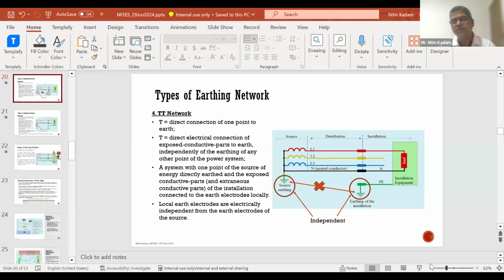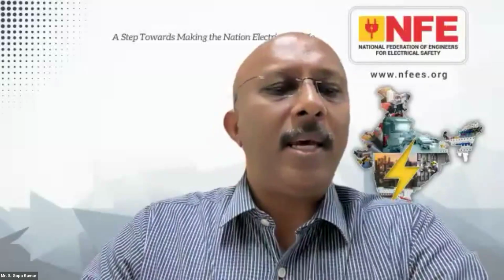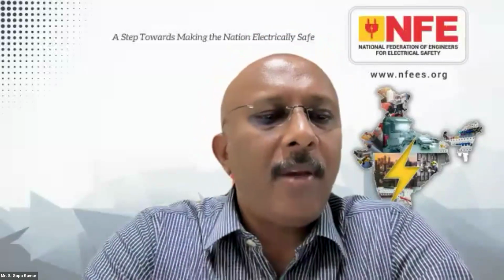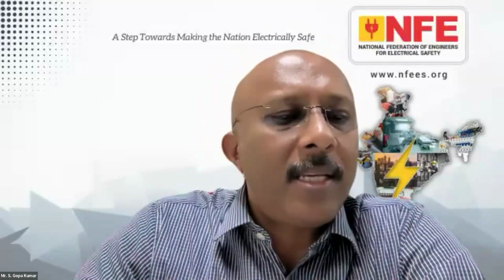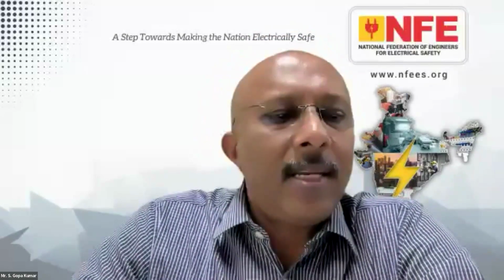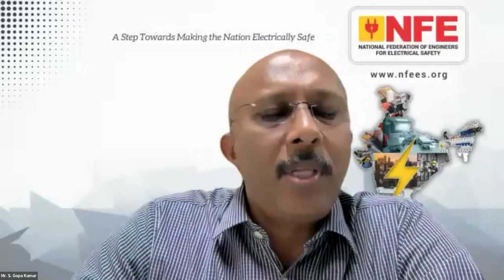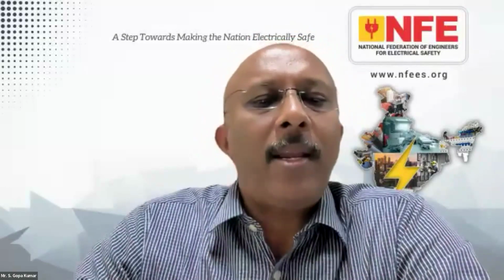This is a good question. Cable armor, yes. In several countries, cable armoring is allowed because cables are installed as per the requirement of the standard. Whereas here, connecting the armor to the earth busbar of the panels is very complicated, and in a lot of cases these connections are not made properly. As a result, the standard doesn't recommend using the armoring. Instead, you use a 5-wire cable.